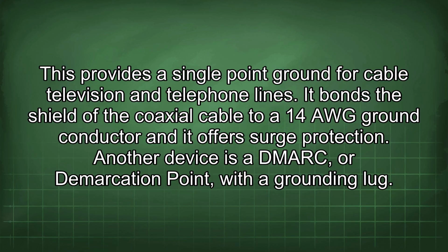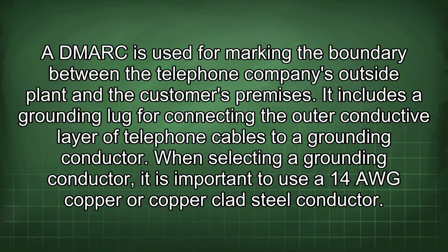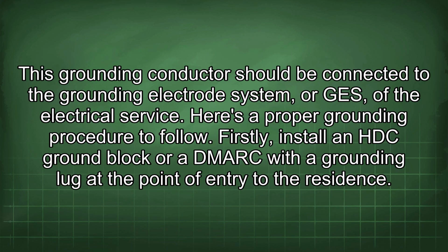Another device is a demarc, or demarcation point, with a grounding lug. A demarc is used for marking the boundary between the telephone company's outside plant and the customer's premises. It includes a grounding lug for connecting the outer conductive layer of telephone cables to a grounding conductor. When selecting a grounding conductor, it is important to use a 14 AWG copper or copper-clad steel conductor. This grounding conductor should be connected to the grounding electrode system, or GES, of the electrical service.